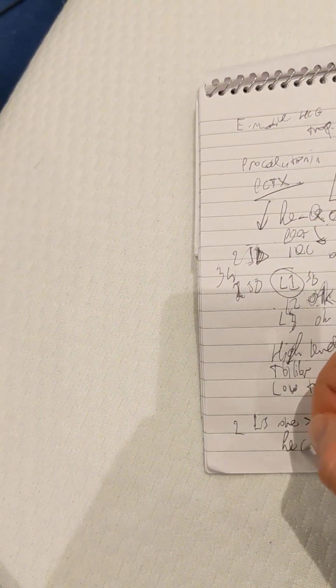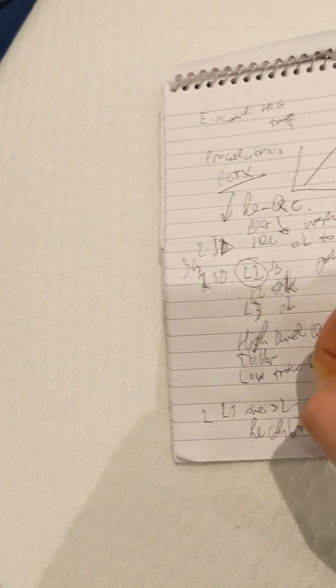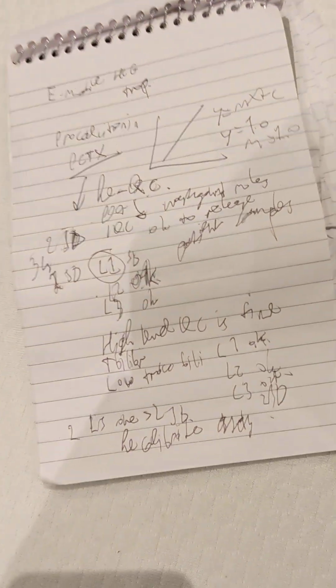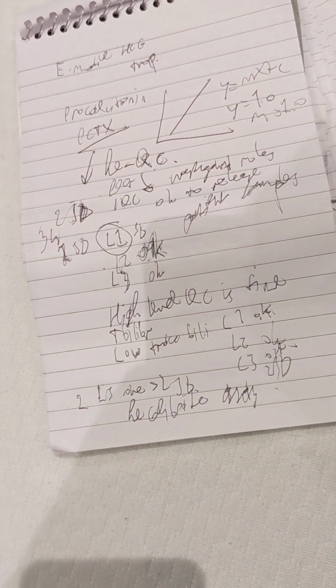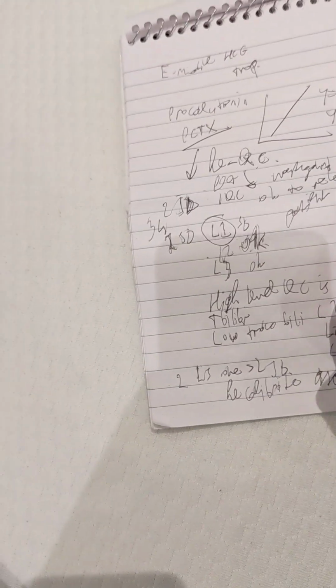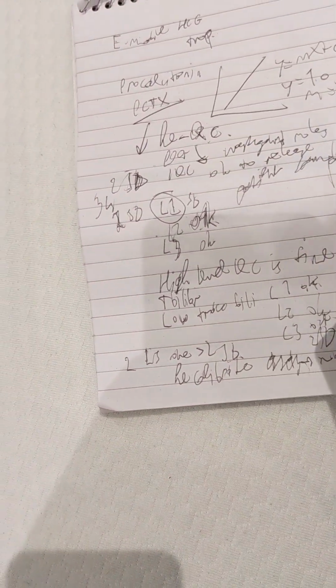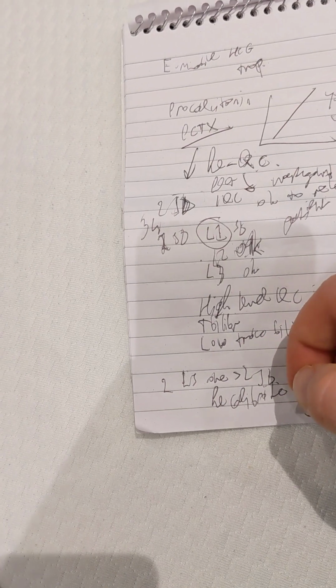That's okay. But if 2 levels are greater than 2 SD on a rerun, you have to recalibrate your biochemistry method. You have to recalibrate it. Then after calibration, test the calibration, then rerun patient samples.